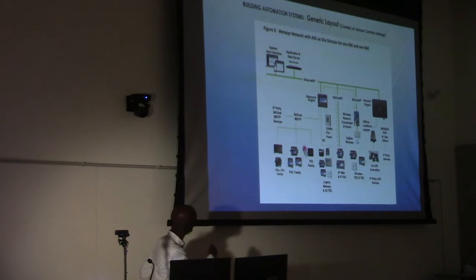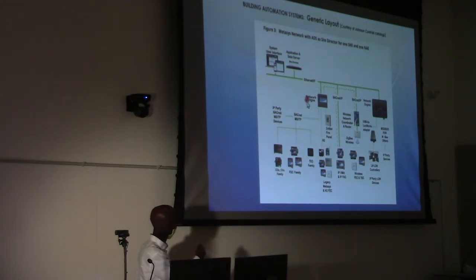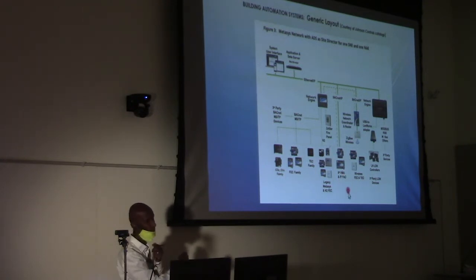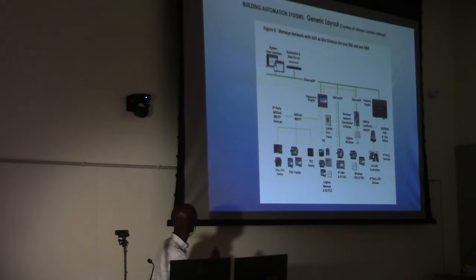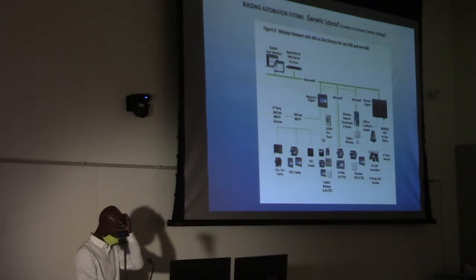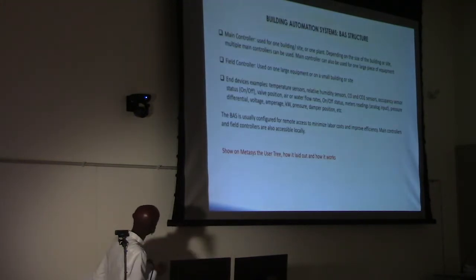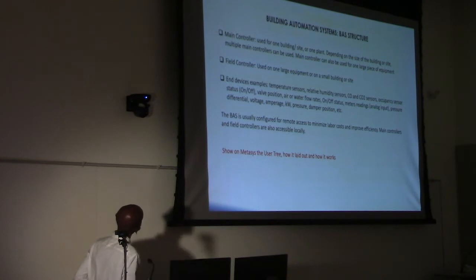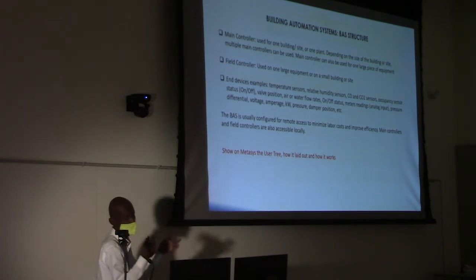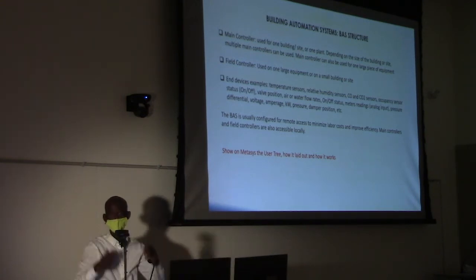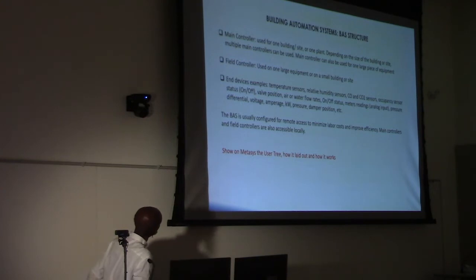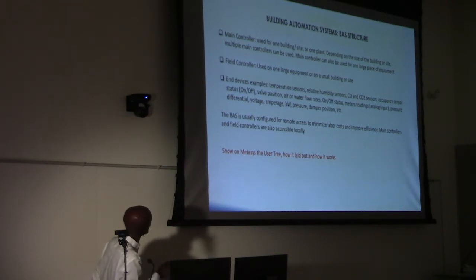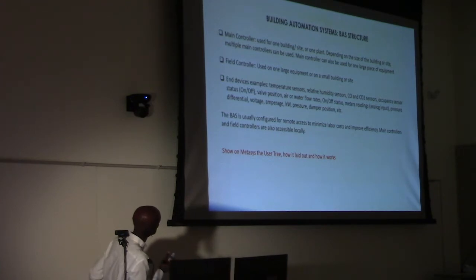Okay, and they communicate by a different communication mode, but it depends also on the age of the equipment, because some may be MSTP, some may be N2, but all these report to the main controllers, which report to this main server. Next. So, quick explanation on how they work. The main controller is used for one building, or one site, or one plant. You can have a main chiller, larger chiller plant, or large power plant. Depending on the size of the building or the size of the site, multiple main controllers can be used. Main controllers can also be used for one large piece of equipment.